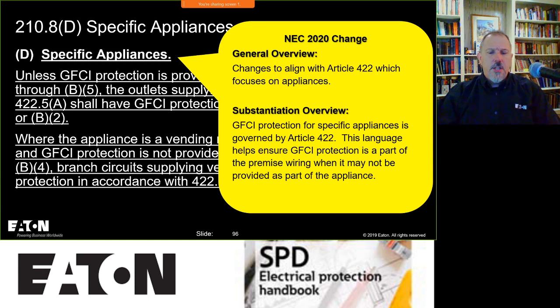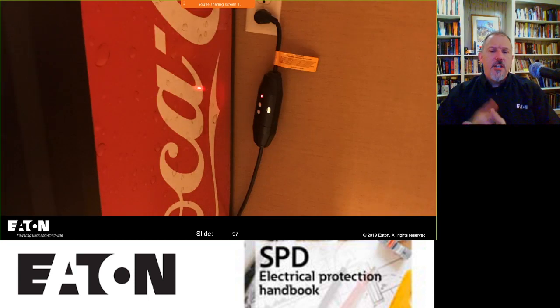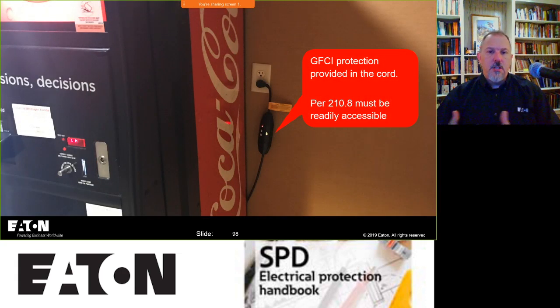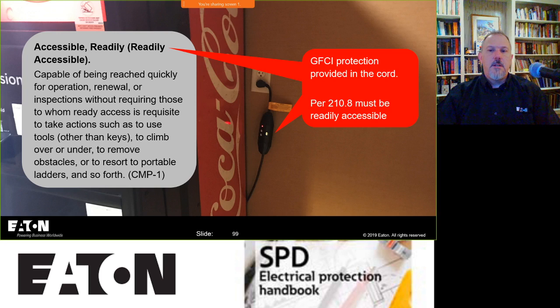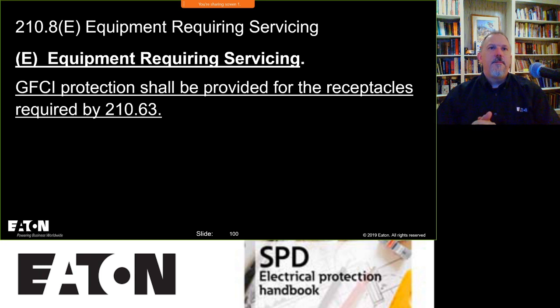What drove a lot of the changes in 422 is this: GFCIs have to be readily accessible, and there's a requirement for soda pop machines or appliances. You take that machine and put the receptacle behind it with the GFCI in the cord, and when you push that machine back, now you have no access to reset and test that GFCI product. That drove a lot of the changes in 422, because it has to be readily accessible based on what's in 210.8, and the definition is you can't move things. That's what made some changes there. So just be mindful of what's going on in 422 as well.